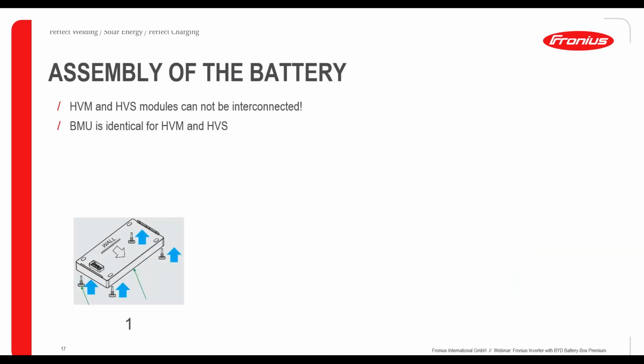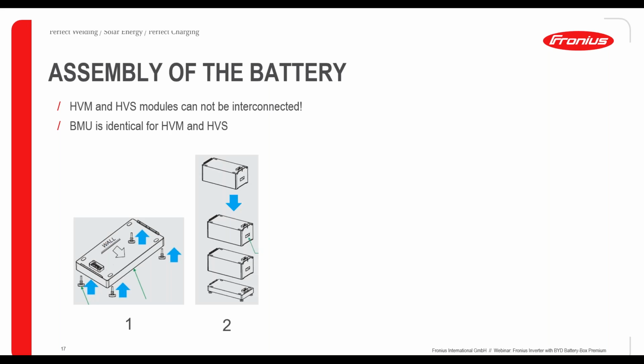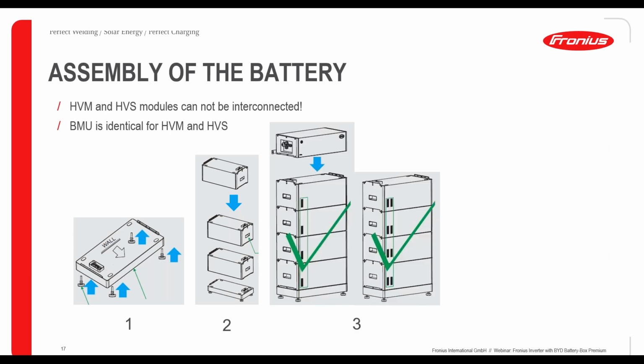Furthermore, of course, you can choose between the HVM and HVS variant, like Sandro told you before. For the installation of the battery modules itself, you first need your ground stand, so the feet that you see beneath. You just place this ground panel on the floor, and then you just have to add up the battery modules in your system. Depending on how many battery modules you're using, you just connect them in series on top of each other. Then you have a screwing installation where you can screw these modules to each other so that they are fixed to each other.